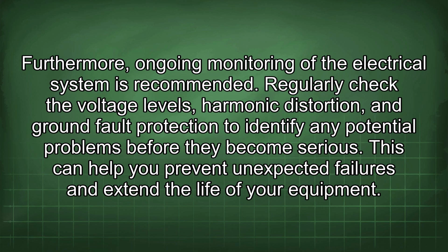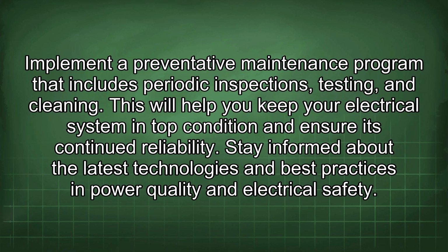Furthermore, ongoing monitoring of the electrical system is recommended. Regularly check the voltage levels, harmonic distortion, and ground fault protection to identify any potential problems before they become serious. This can help you prevent unexpected failures and extend the life of your equipment. Implement a preventative maintenance program that includes periodic inspections, testing, and cleaning. This will help you keep your electrical system in top condition and ensure its continued reliability.